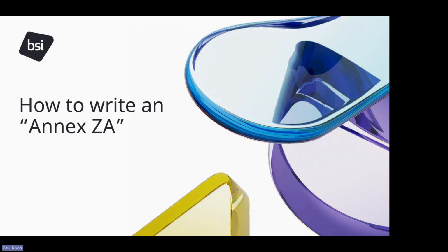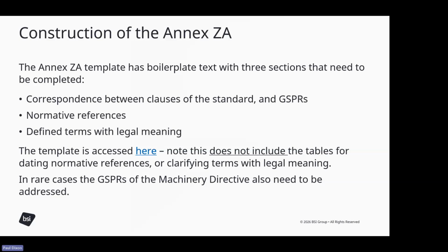So, how to write an Annex ZA? The Annex ZA template is essentially boilerplate text with 3 sections that need to be completed, or up to 3 sections that need to be completed. There is a table for correspondence between the clauses of the standard and the general safety and performance requirements of the MDR. There's a table to address normative references, and in particular the dating of references and the European edition of references. And there is a table to cover defined terms that are defined in the standard but also have legal meaning under MDR. So that particularly means if you have a definition in clause 3 of your standard that conflicts with a definition in Article 2 of the medical device regulation.